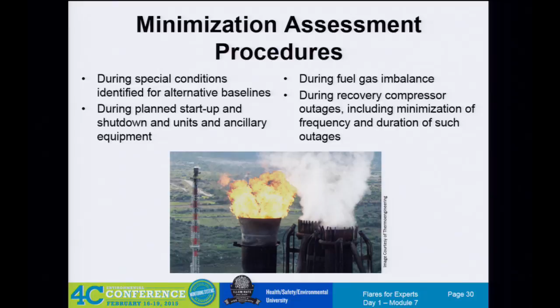Okay, so the baseline flow determination. One thing, though, is this is supposed to be determined after you've done your minimization assessment. So you're supposed to have gone through and found all the places where you can minimize flow, and then you're supposed to set your baseline. You're not supposed to set a baseline and then figure out where you can minimize stuff. It doesn't have to include pilot or purge gas, but it can. Especially, it doesn't have to include the purge gas if it's consistent. If you have a variable purge gas, then yes, you're going to want to put that in your baseline.